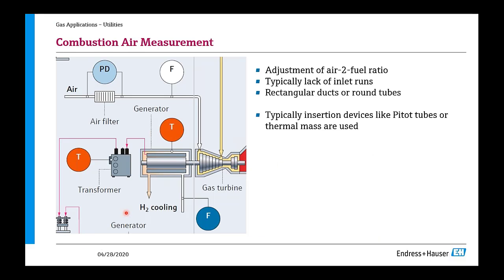When it comes to combustion air, you measure this to adjust the air to fuel ratio. Typically here you have a lack of inlet runs. You find rectangular ducts or round tubes here, and typically you're using insertion devices like Pitot tubes or thermal mass flow meters.